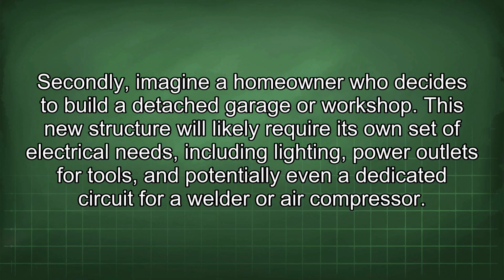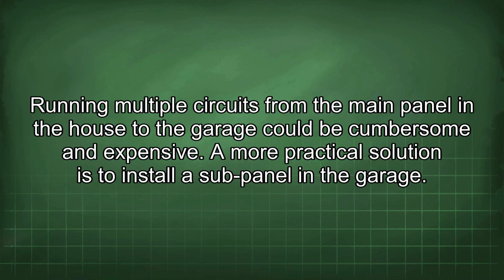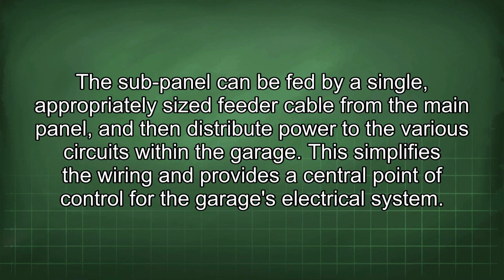Secondly, imagine a homeowner who decides to build a detached garage or workshop. This new structure will likely require its own set of electrical needs, including lighting, power outlets for tools, and potentially even a dedicated circuit for a welder or air compressor. Running multiple circuits from the main panel in the house to the garage could be cumbersome and expensive. A more practical solution is to install a sub-panel in the garage. The sub-panel can be fed by a single, appropriately sized feeder cable from the main panel, and then distribute power to the various circuits within the garage. This simplifies the wiring and provides a central point of control for the garage's electrical system.